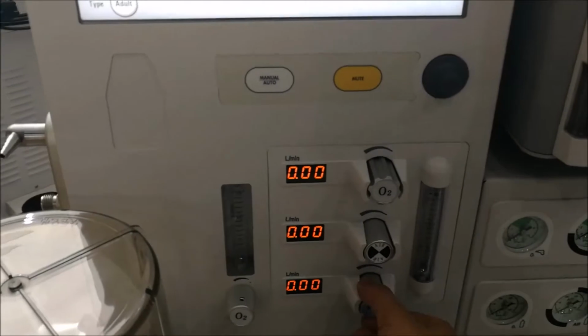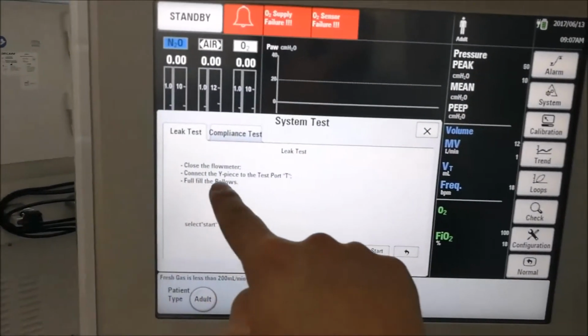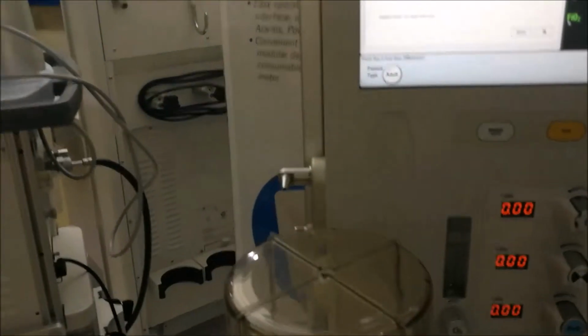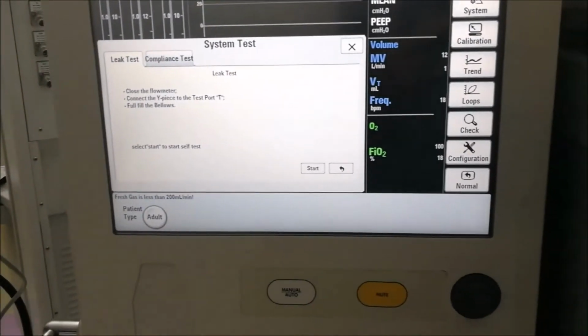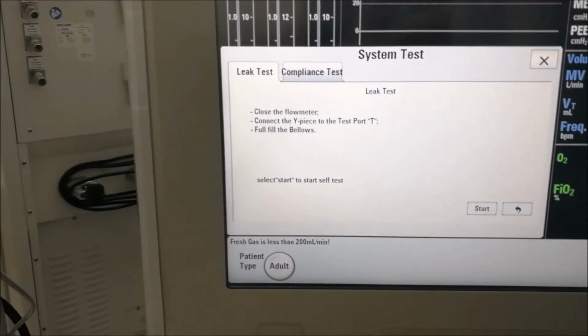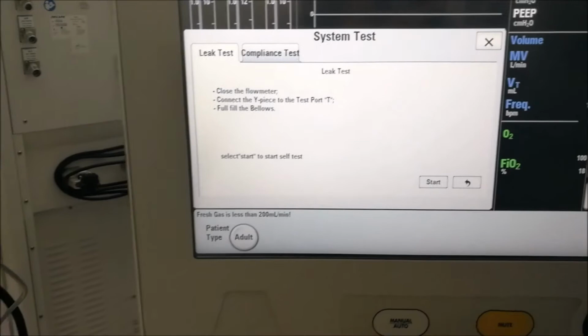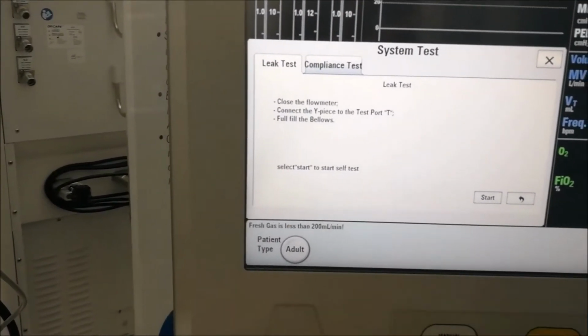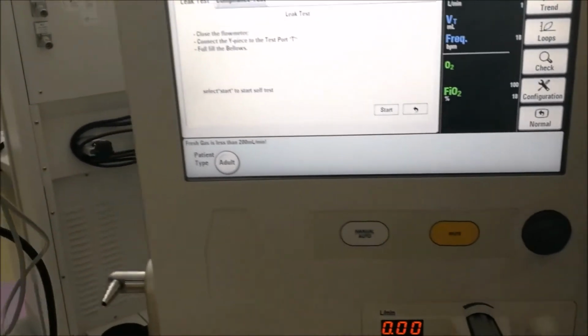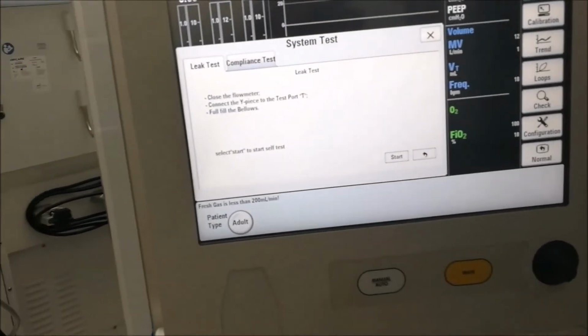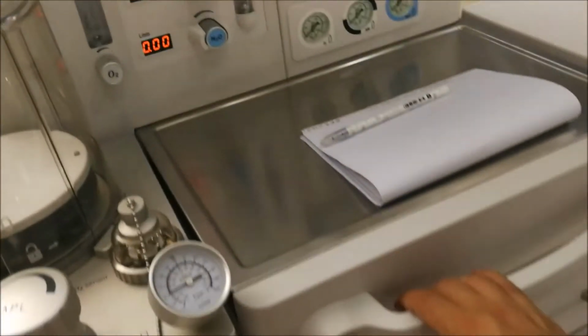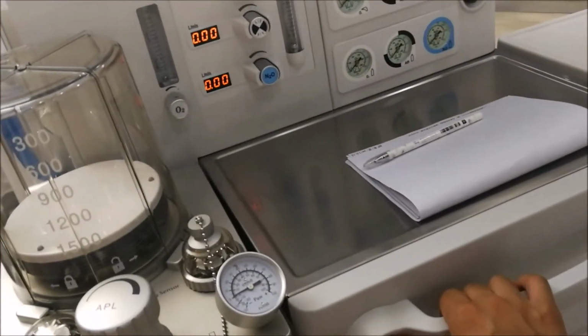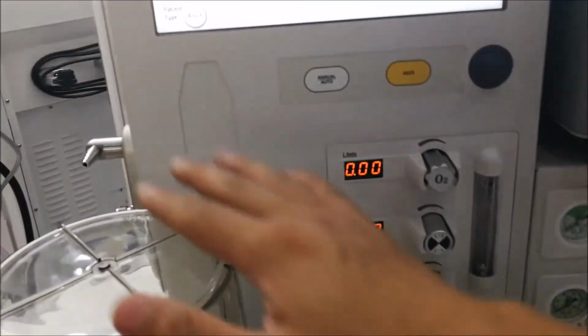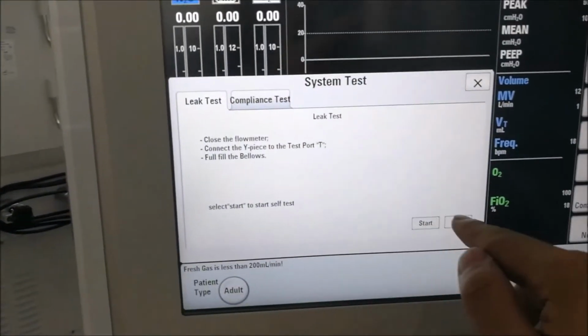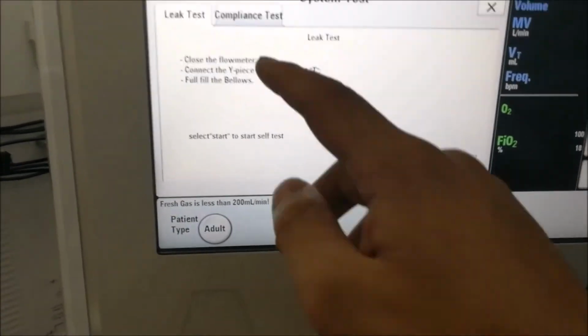Okay, when it's closed, second, connect the Y-piece to the test port, just like what we showed in the manual test. It's the same. And the third is fill the bellows. If you talk about filling the bellows, we just do this, push it, and the bellows will go up. If we finish it and press done, it will test by itself.